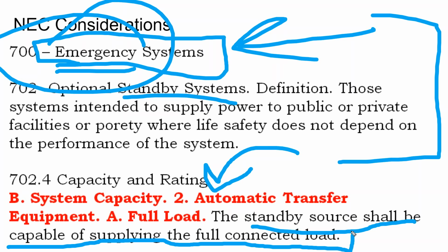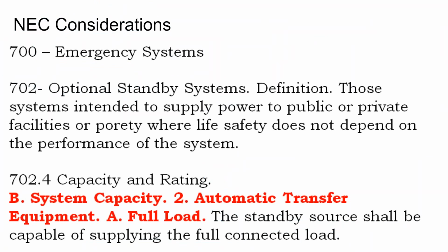And while we have manual transfer switches, where I say, okay, during Hurricane Sandy, I'm going to go buy a generator and wire it up to my service panel, and I'm going to manually flick the interlock switch and turn my generator on and supply my whole house, and I'm just going to make sure that if I have a 10 kilowatt generator and I have 40 kilowatts of breakers, I manage my electricity so I can supply the power to it. This is an automatic transfer switch requirement. And so we see a lot of automatic transfer switches in these grid-tied battery inverters, and they're not supplying the whole house because they're not rated to.